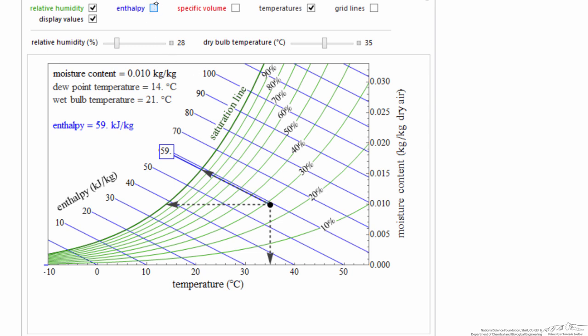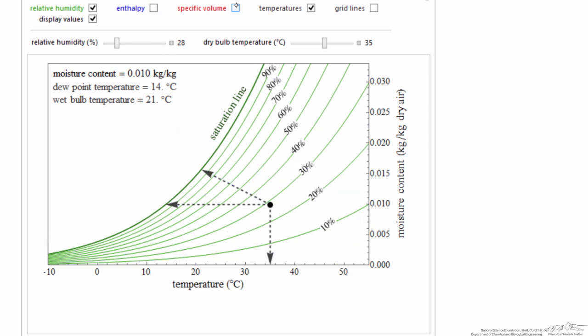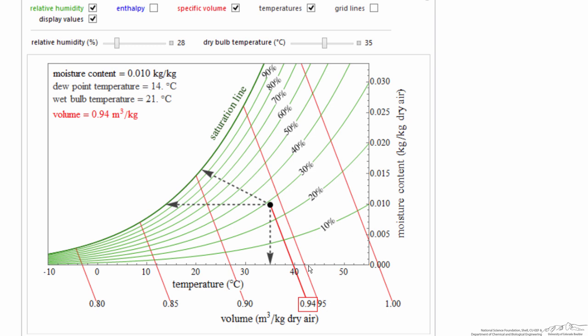Let's remove this so it's not too complicated, and let's look at specific volume. So for this point, specific volume, or humid volume, probably a better term, is the number of cubic meters per kilogram of dry air. So 0.94 cubic meters per kilogram of dry air.